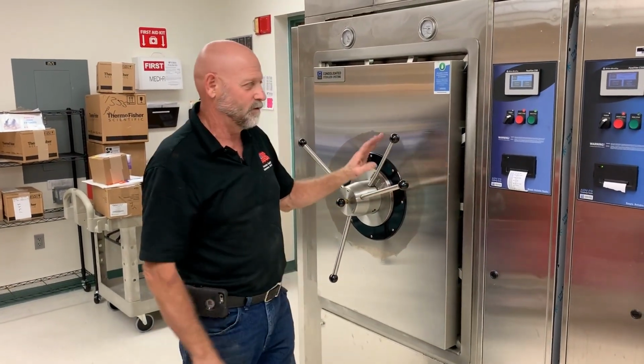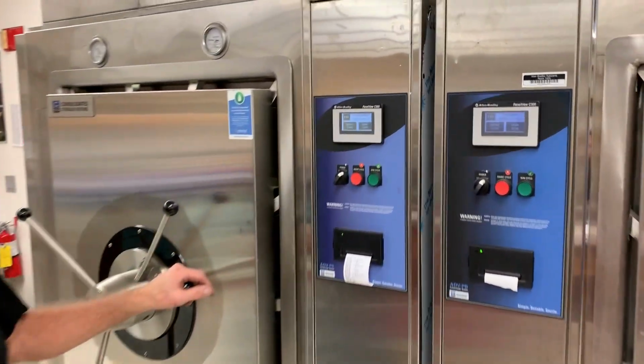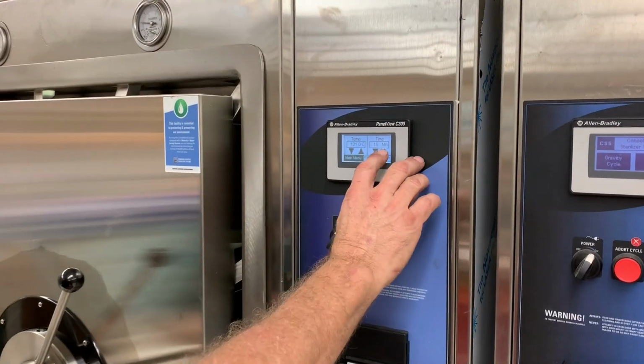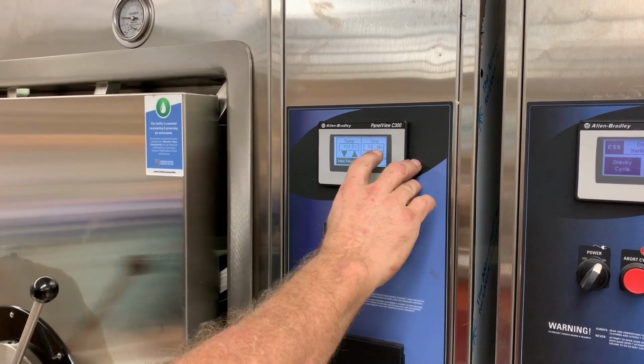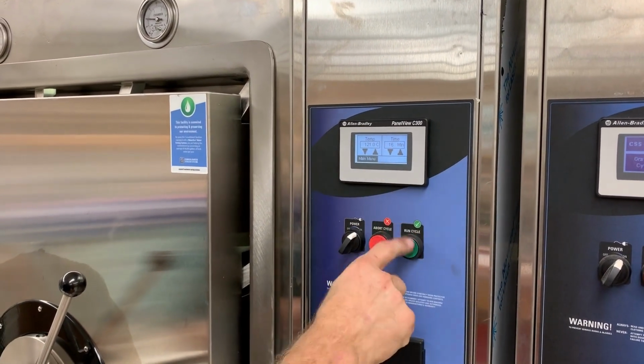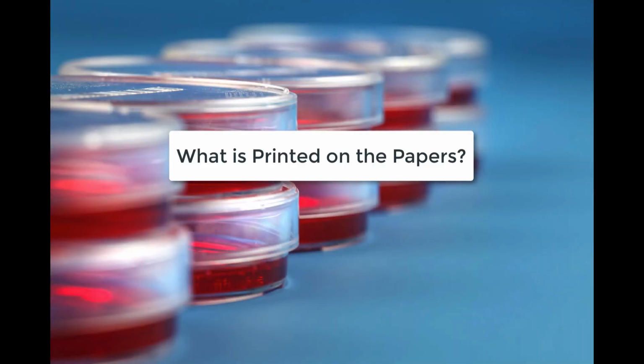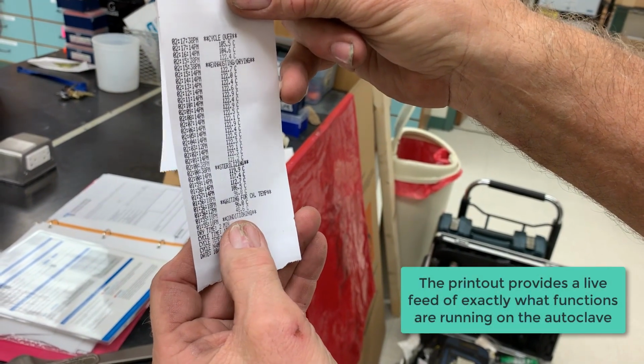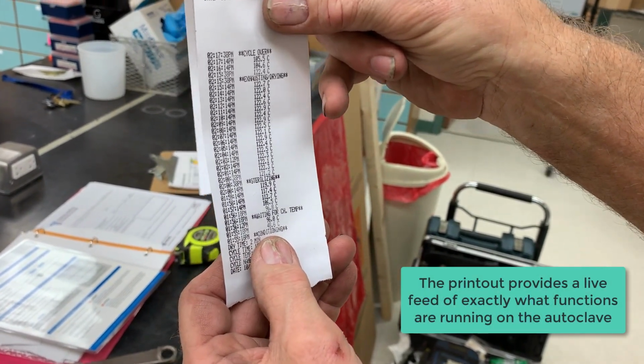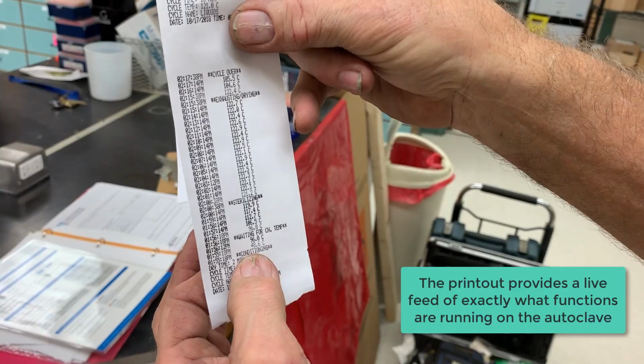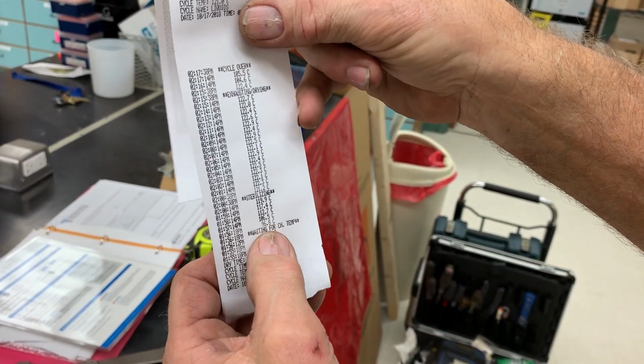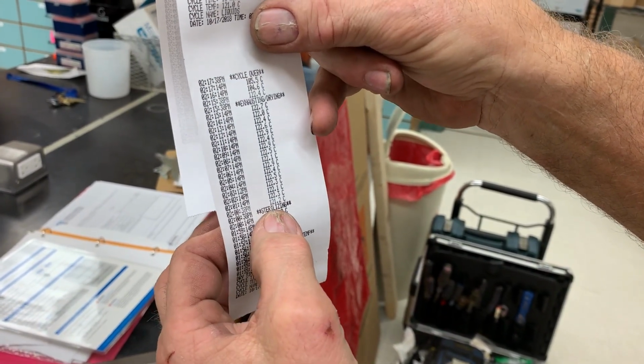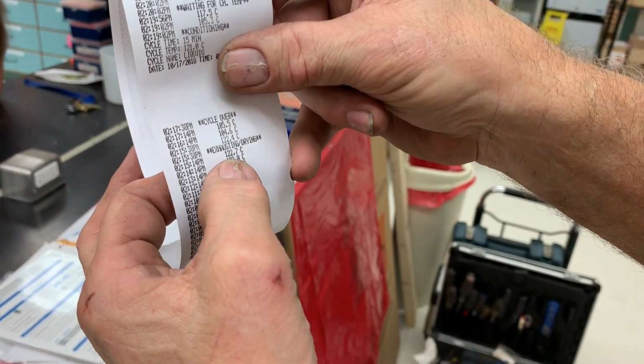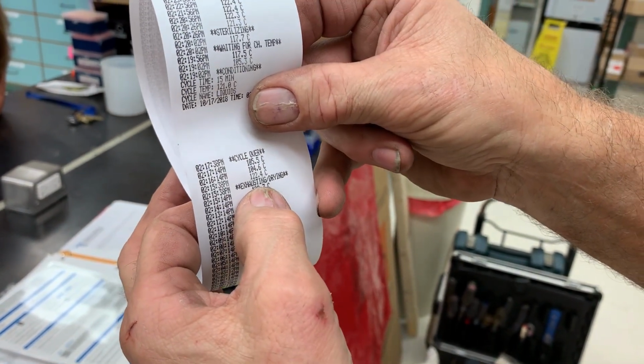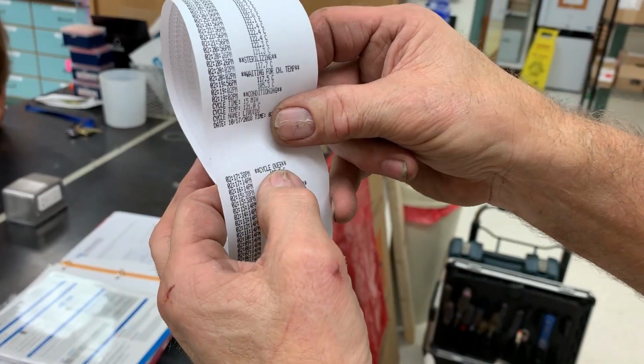Okay, if you're doing liquid, you do the same thing. You go to liquid, you set time. That's all you would set is time. And then you hit go. It gives you the time and date. It tells you what point the machine is in. It goes to conditioning, then it's waiting for temperature, then it's sterilizing, and it sterilizes all the way up to a time where it hits exhaust. It exhausts and then tells you the cycle's over.